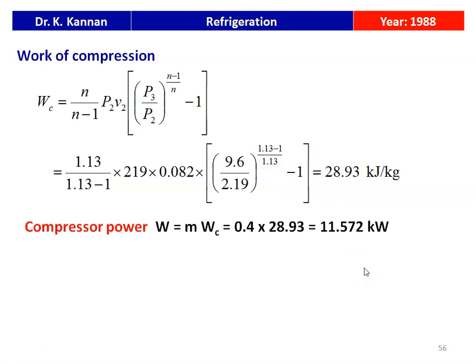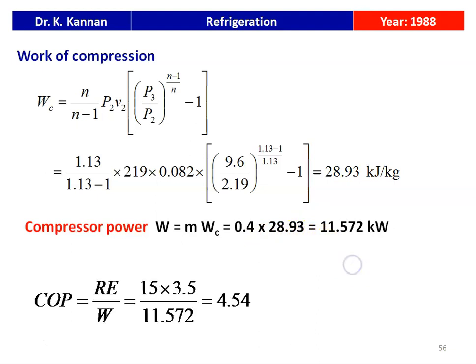The compressor power equals compressor work done multiplied by mass flow rate: 0.4 × 28.93 = 11.572 kW. The COP of the cycle equals refrigeration effect divided by work done: (15 × 3.5) / 11.572 = 4.54. So, the compressor power is 11.572 kW and COP = 4.54.